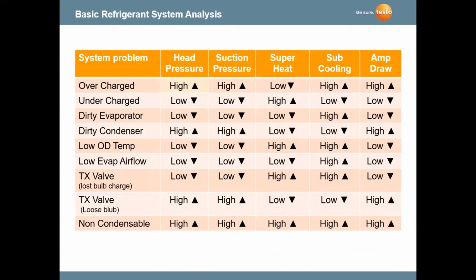Other things you can look at on digital gauges together is looking at the pressures, head pressure, suction pressure, superheat, subcooling. If you're doing amp draws, you can look at doing a system analysis and looking at some of the symptoms that you have that you can diagnose a lot quicker.